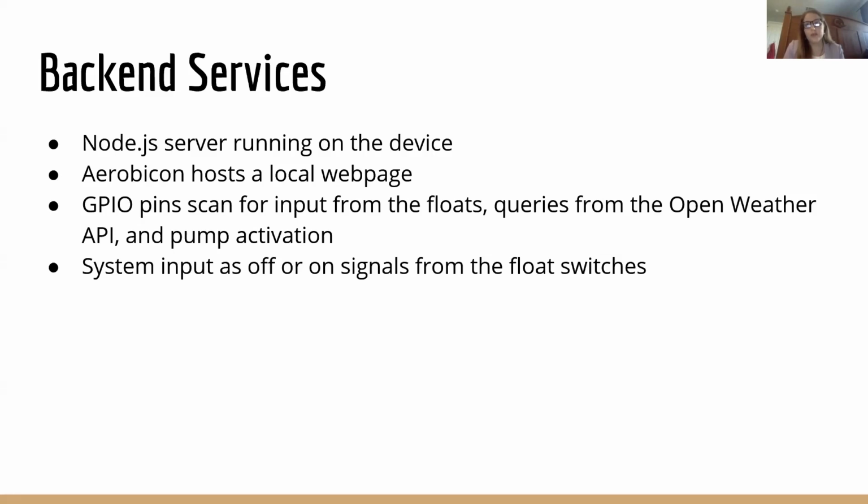The input from the septic system will be in the form of on and off signals from multiple float switches that are installed in the tanks. The float switches will indicate the water level of the second and third tanks. If the tank sends an on signal, it means the water level has reached the float switch. Each septic system typically has a maximum of 4 switches total, with about 2 switches per tank. This can be adjusted if it's a unique tank or a unique system that has more than 3 tanks, but the average one only has 2 tanks.